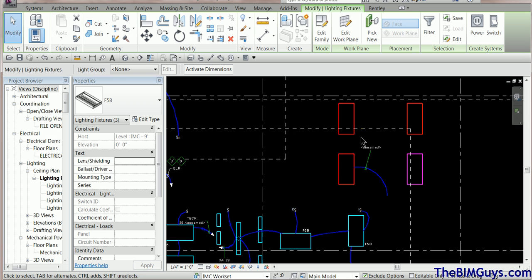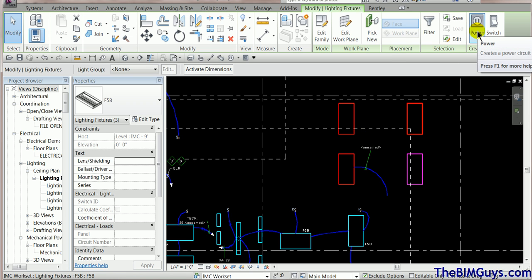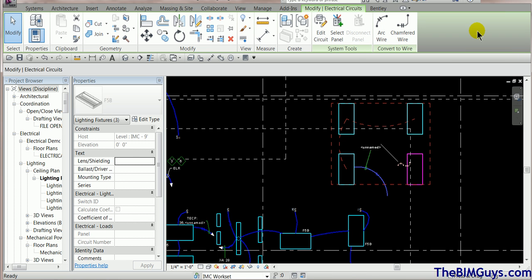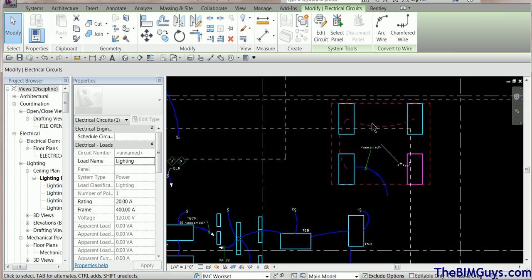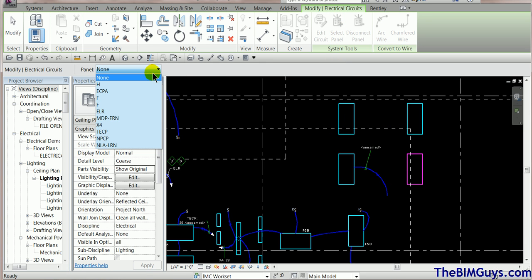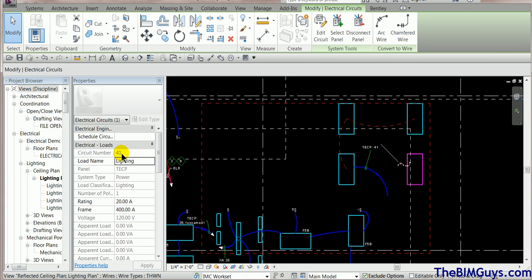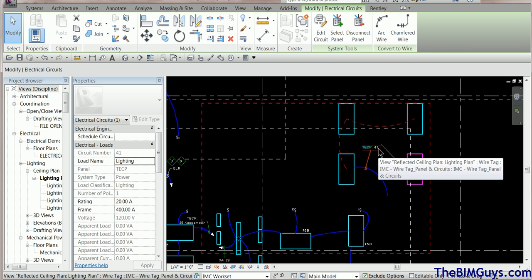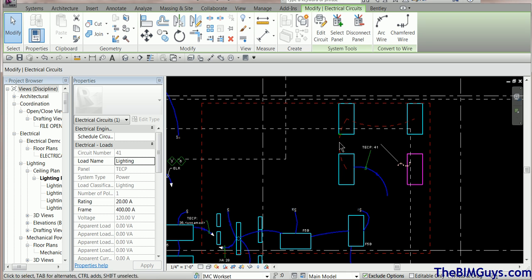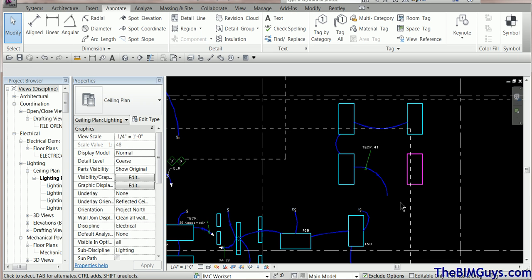Now these three are selected — it's time to power them up. You'll see a power icon in the ribbon. I hit Power, and Revit shows the objects that will be grouped together. I hit Select Panel, drop down the list, and choose the TECP panel. Revit then assigns them the next available circuit — the last was 38, now it's 41. It also asks if I want to add the wire at this time. Clicking yes adds the wire. That is the proper way to add a circuit.